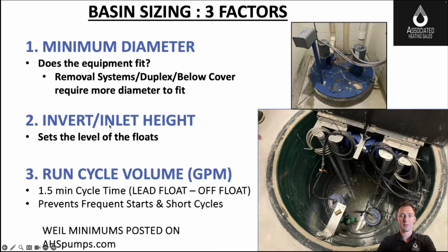Okay, last factor for the sump pump system. Hey, I've got my duty point. I'd really like to know what size basin. This is crucial for the engineers when they're looking at a footprint of a mechanical room. I don't have much room. I got 3 feet here. What size is the cover? To give any idea, for a 2-inch system, typically our minimum for a duplex is going to be somewhere around 3 feet. For a 3 or 4-inch system, you're at 4 feet, 4.5 feet. So it becomes important to pre-plan everything out here.